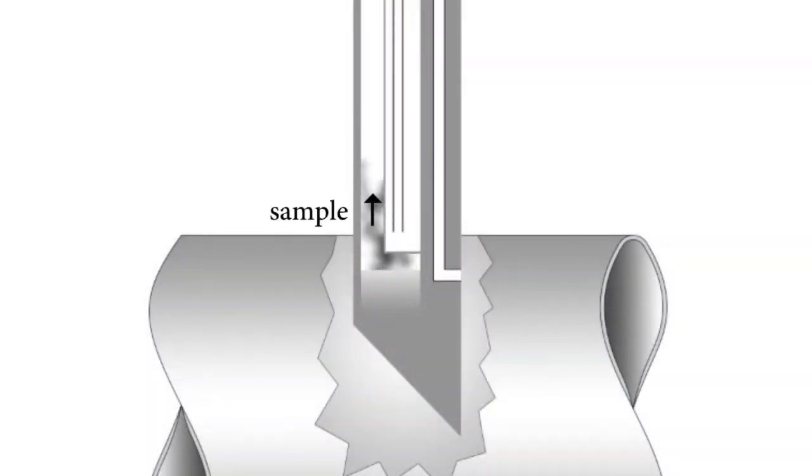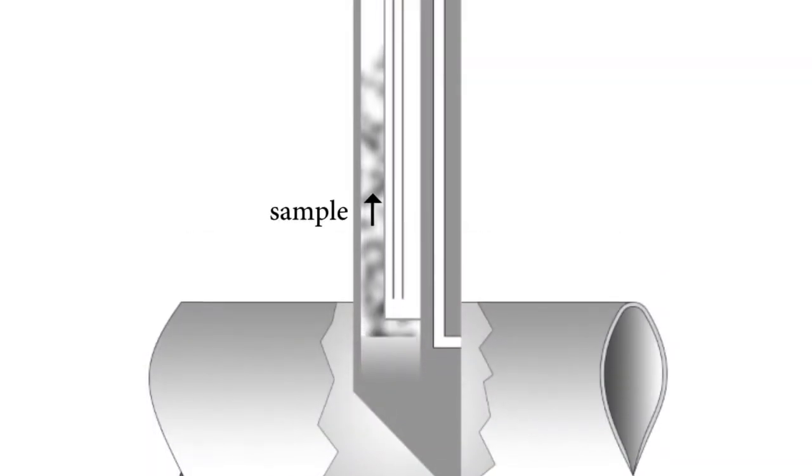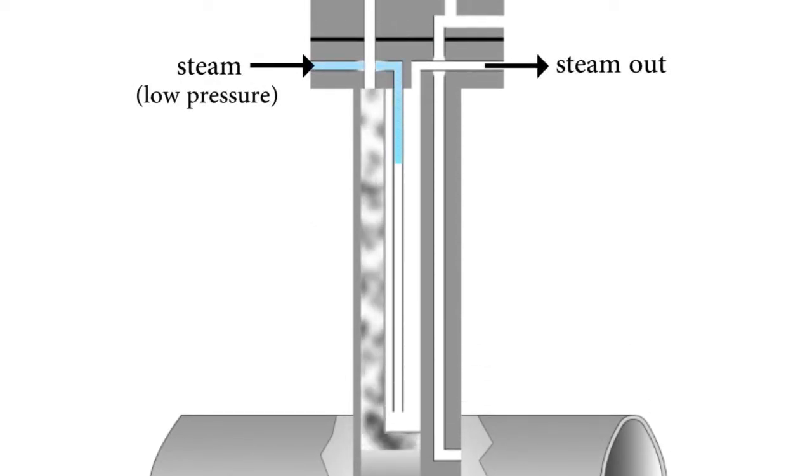Gas enters the angled inlet tip and gets pulled up the probe body by an aspirator. The design uses low pressure steam to actively condense elemental sulfur out of the sample in a controlled manner.